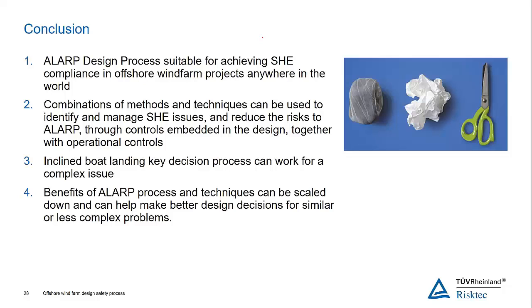Just to reinforce what you said there, Richard, in the oil and gas sector we have the potential for major accident hazards, driven by the hydrocarbons being processed. There's legislation that requires the formal documentation and submission of a safety case to demonstrate that risks have been reduced to ALARP, with assessment and subsequent inspections. In the wind sector, it might be viewed as a high hazard sector rather than a major accident hazard sector. But the process after that is exactly the same. It's a risk assessment based process. There will be HSE assessment and inspections, and therefore you're taking a fit for purpose approach. You just don't have to formally submit a safety case document to the regulator.